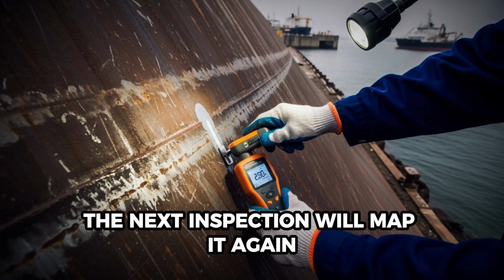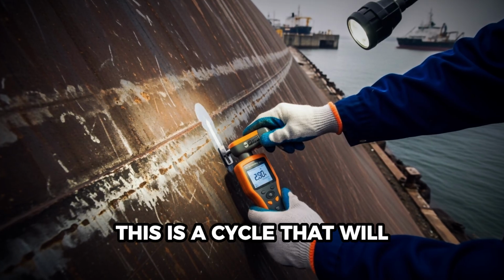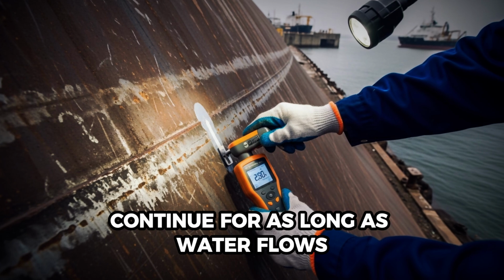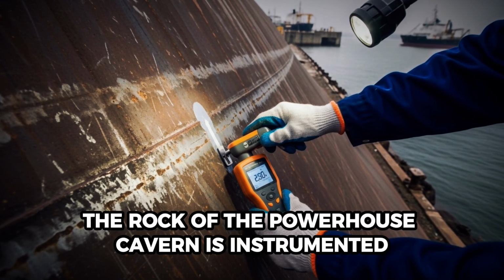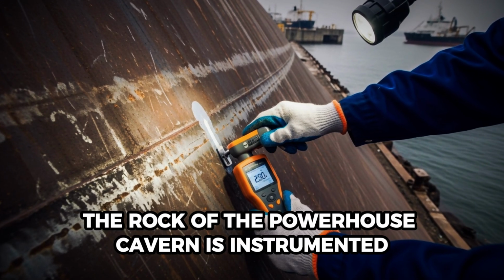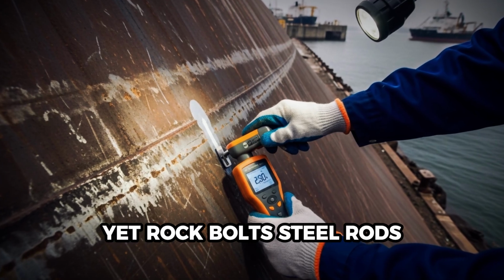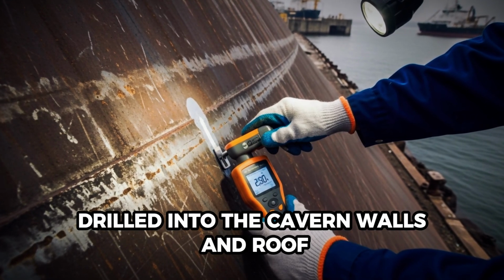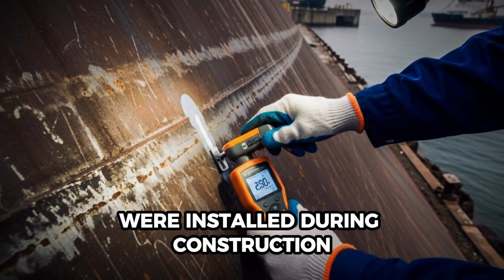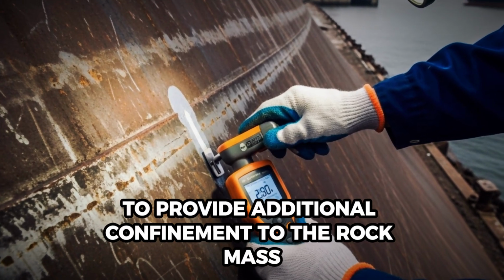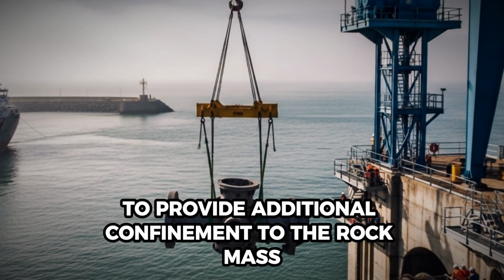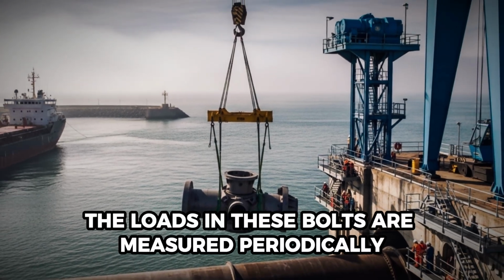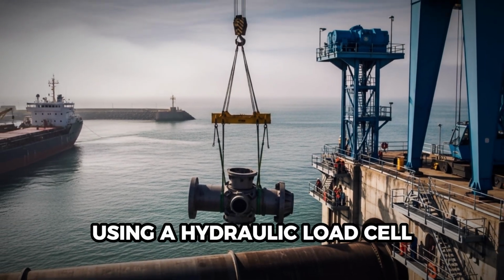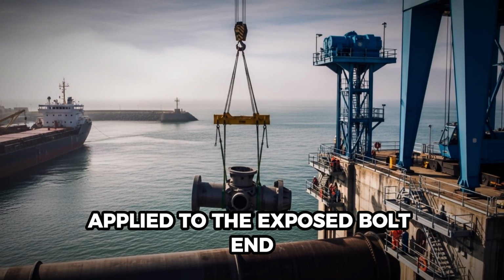The next inspection will map it again. This is a cycle that will continue for as long as water flows through these tunnels. The rock of the powerhouse cavern is instrumented. It had rock bolts, steel rods grouted into boreholes drilled into the cavern walls and roof, installed during construction to provide additional confinement to the rock mass. The loads in these bolts are measured periodically using a hydraulic load cell applied to the exposed bolt end.